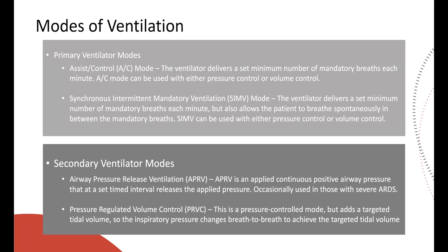Pressure regulated volume control, or PRVC, is a dual mode of ventilation that allows you to target a tidal volume and then uses pressure control ventilation to achieve that breath. Breath to breath, it looks at the tidal volume: if it didn't reach the target, it increases the pressure on the next breath; if it exceeded the target, it decreases the pressure on the next breath — to avoid overshooting or under-delivering.